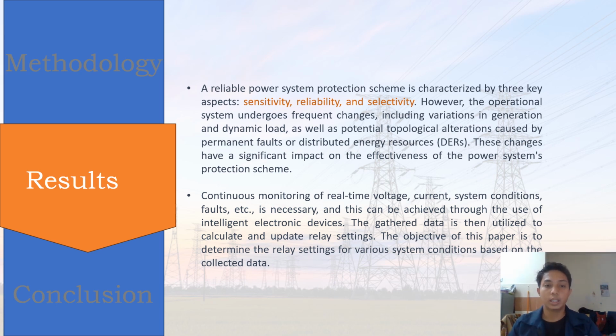The result is a reliable power system protection scheme characterized by three key aspects. First, sensitivity. Second, reliability and selectivity. However, the operational system undergoes frequent changes, including variation in generation and dynamic load, as well as potential topological alterations caused by permanent faults or distributed energy resources. These changes have a significant impact on the effectiveness of the power system protection scheme.